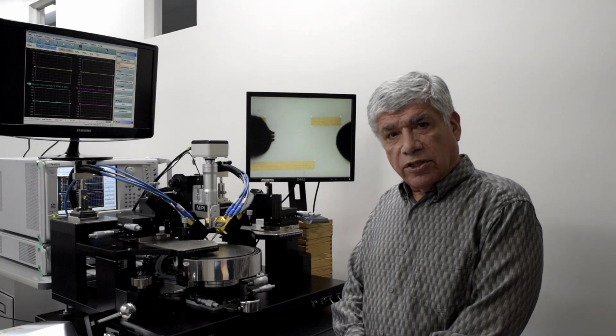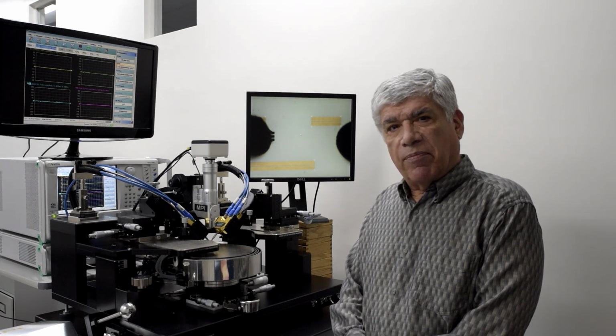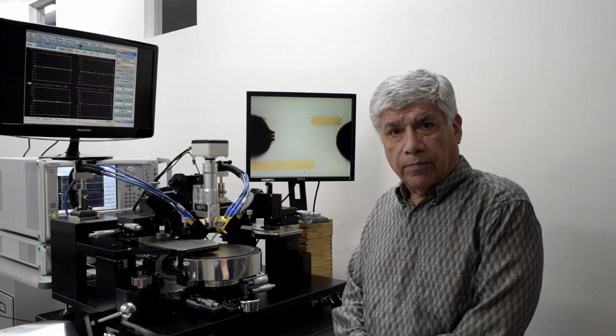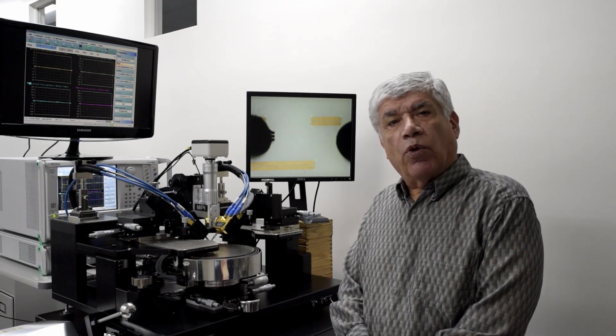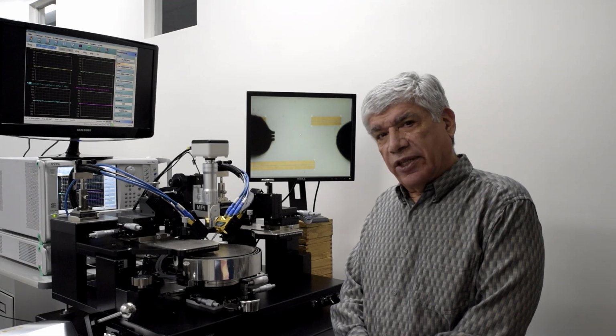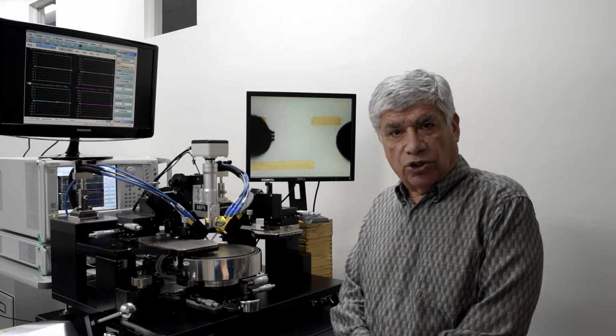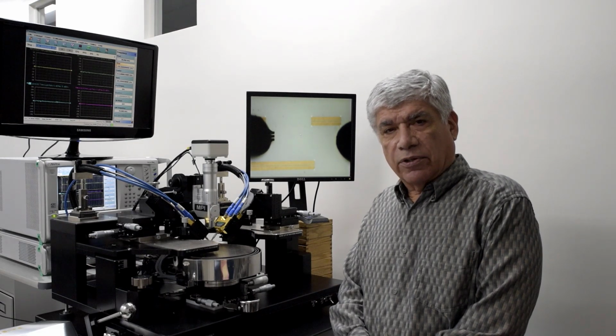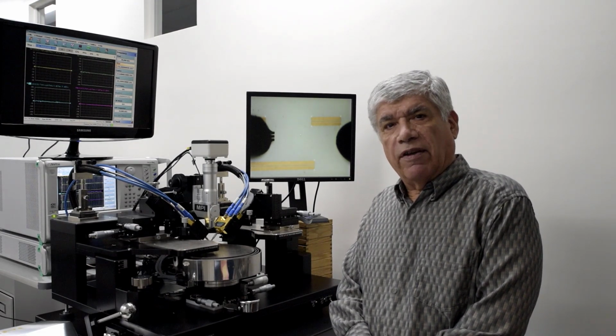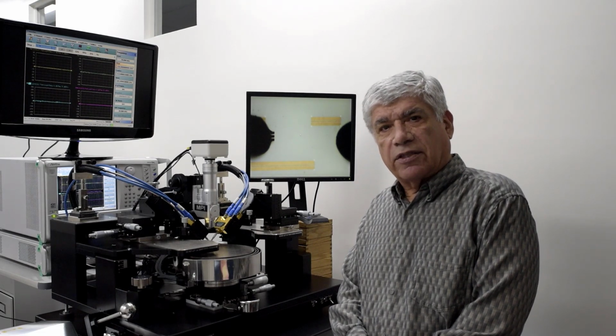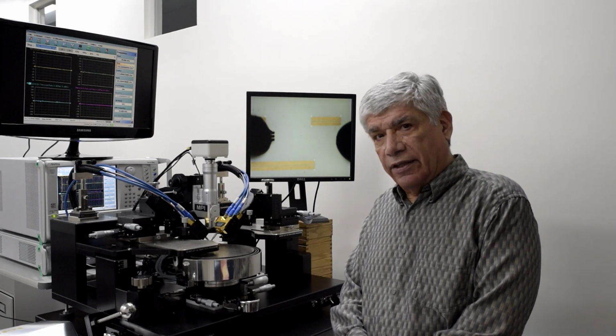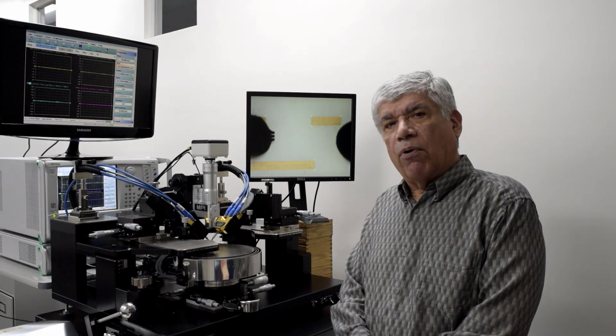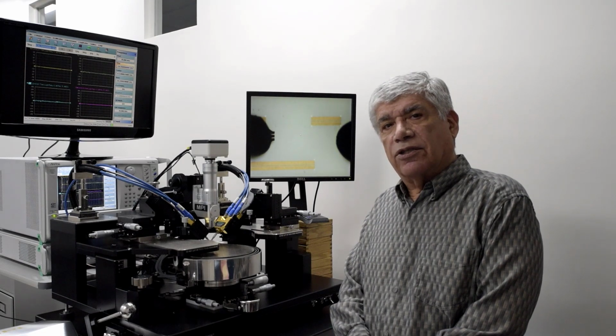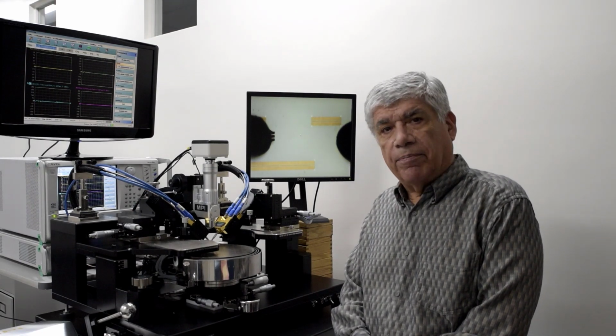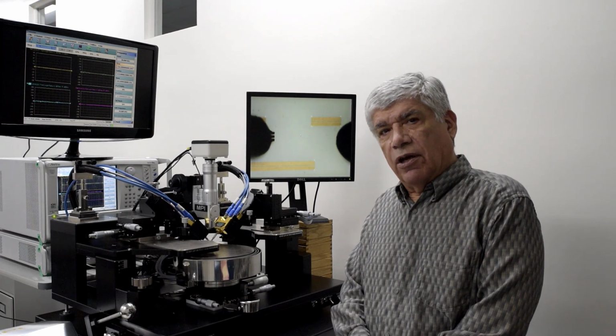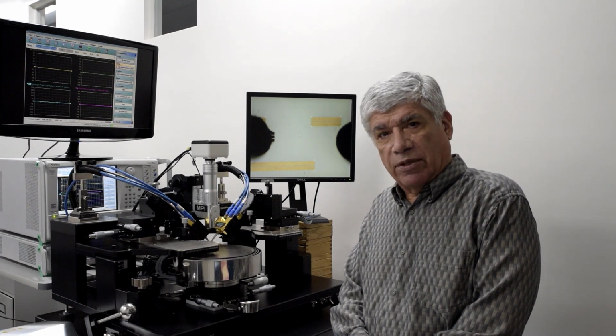In this video, we focus on the hardware aspects when evaluating measurement stability of a VNA broadband system. One of the first things to consider is removing the probes from the test port of the frequency extension modules and attaching coaxial shorts and throughs on the test ports of those modules in order to perform the evaluation and eliminate the effects of probes, positioners, and probe landings. Another important part of the evaluation is to consider the temperature variations in the lab. So you'd want to perform this evaluation during a time when the temperature of the lab is reasonably stable.